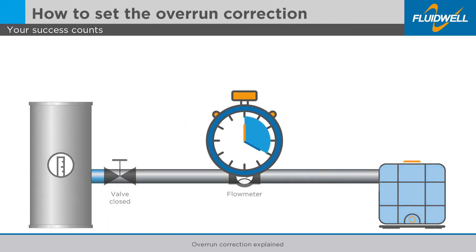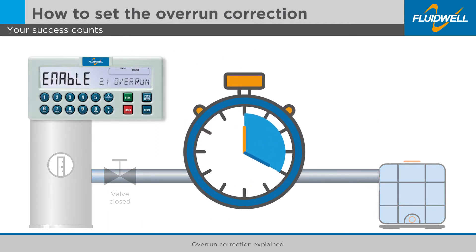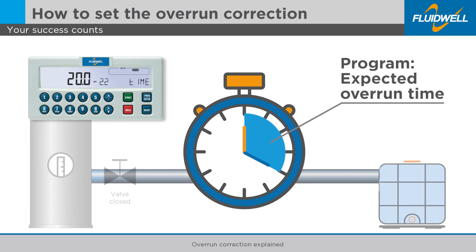How to set the overrun correction? The amount of time in seconds that needs to be programmed is the expected time required by the system to stop the batch process after the control output has deactivated. It may be necessary to add a little extra time to avoid an incorrect overrun correction and prevent spills.